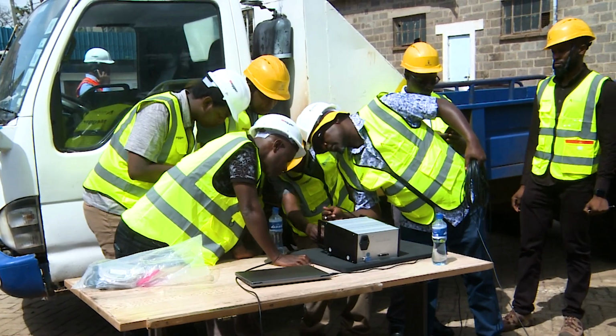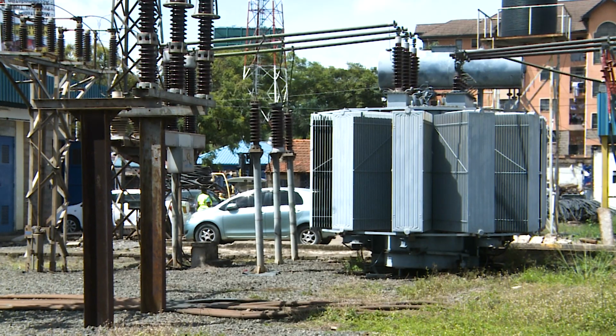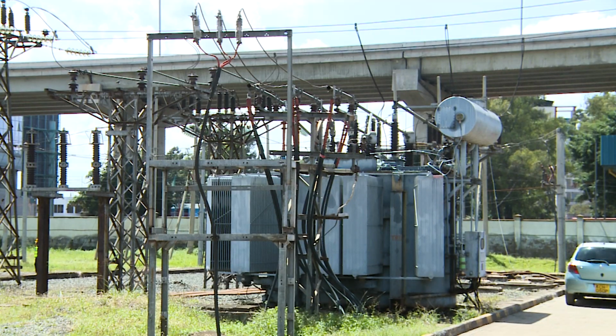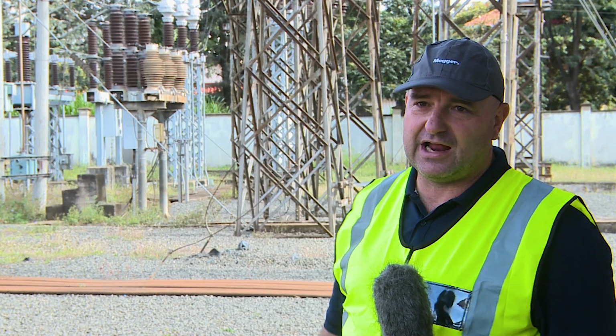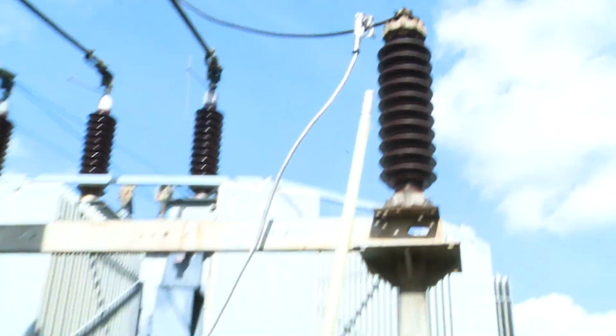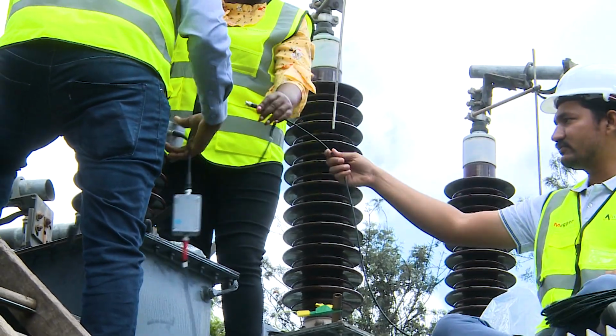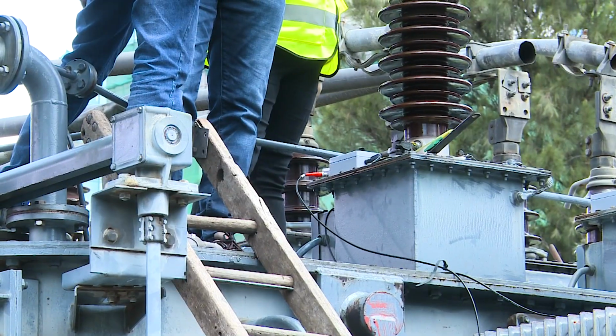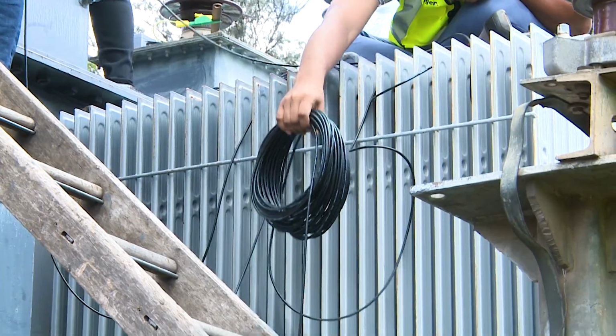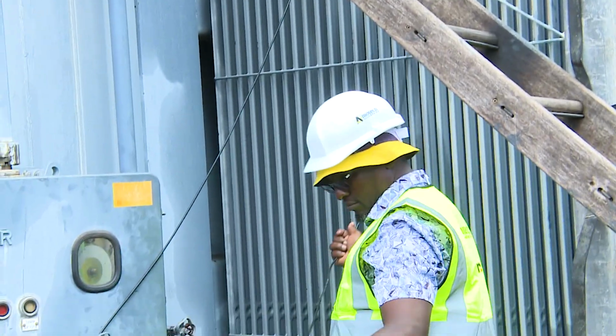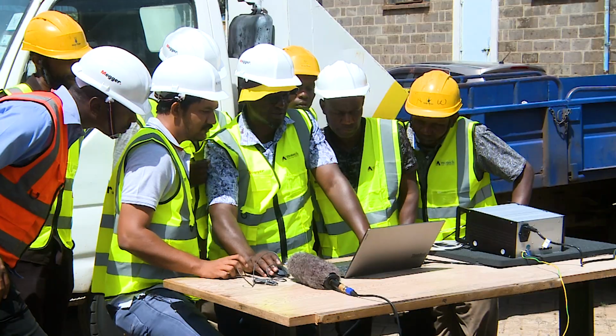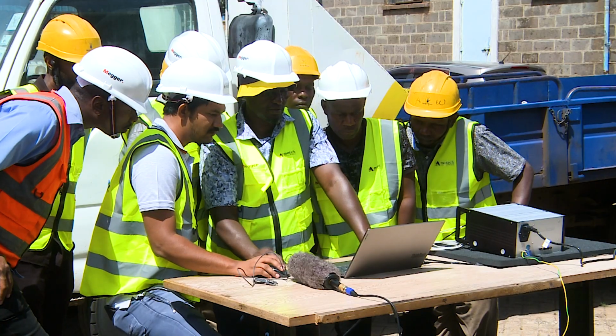This is a very crucial test to do because it is the first indication of possible insulation degradation or failure inside electrical assets. As you can hear, the transformers are live at the moment. We are waiting for Kenya Power to isolate. Once the transformer is isolated, we will connect our accessories to the measuring points on the transformer. Then we will connect the system, perform a calibration, and re-energize the transformer to perform a live PD measurement on an actual working transformer.